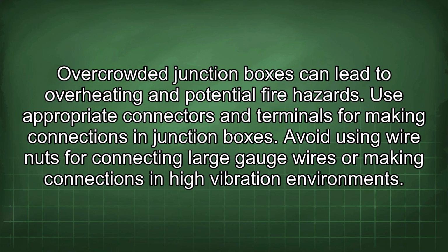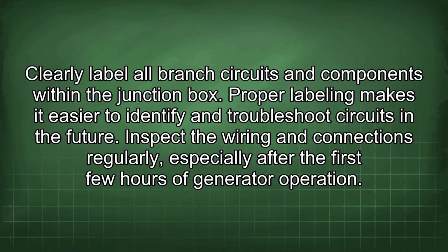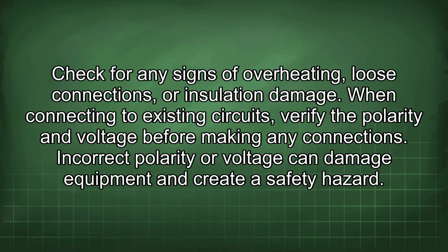Use appropriate connectors and terminals for making connections in junction boxes. Avoid using wire nuts for connecting large gauge wires or making connections in high vibration environments. Clearly label all branch circuits and components within the junction box. Proper labeling makes it easier to identify and troubleshoot circuits in the future. Inspect the wiring and connections regularly, especially after the first few hours of generator operation. Check for any signs of overheating, loose connections, or insulation damage.